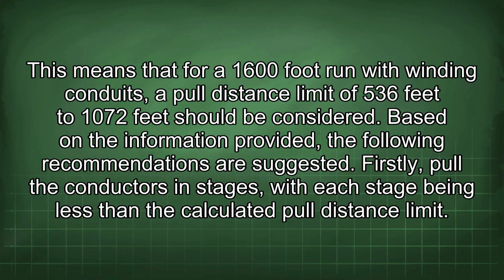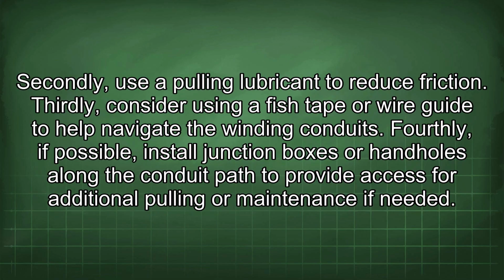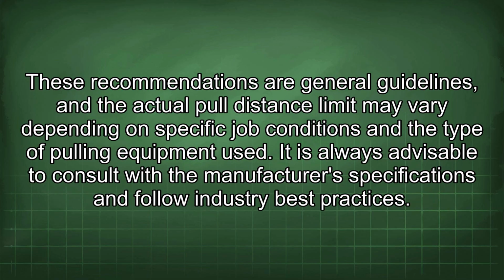Firstly, pull the conductors in stages, with each stage being less than the calculated pull distance limit. Secondly, use a pulling lubricant to reduce friction. Thirdly, consider using a fish tape or wire guide to help navigate the winding conduits. Fourthly, if possible, install junction boxes or handholes along the conduit path to provide access for additional pulling or maintenance if needed. These recommendations are general guidelines, and the actual pull distance limit may vary depending on specific job conditions and the type of pulling equipment used. It is always advisable to consult with the manufacturer's specifications and follow industry best practices.